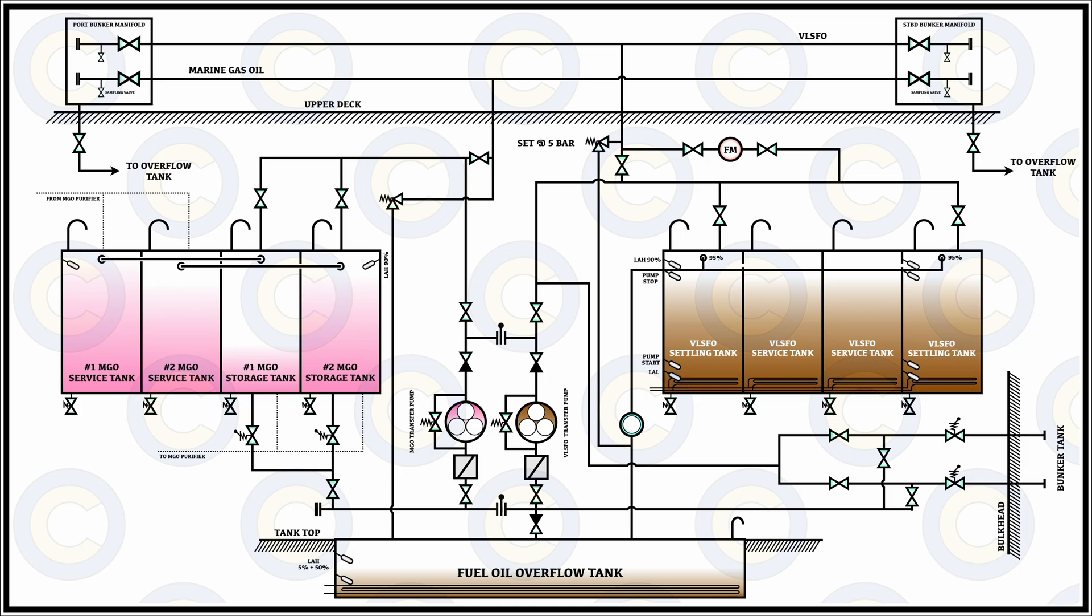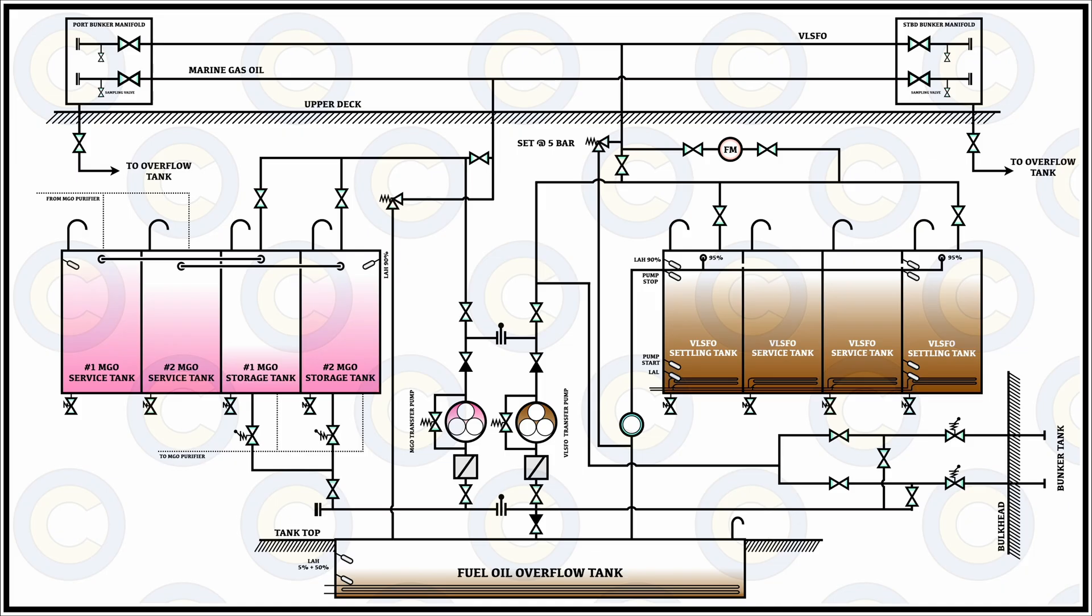Let's say if I was to have certain bunker amount or quantity in my storage tank one and I want to transfer the oil into storage tank two, then basically I line up the suction or the outlet valve - by suction I mean the suction to the pump and by outlet I mean the outlet of the tank. This particular valve, and then as I described earlier the line up, and then opening the filling valve of the number two storage tank - that is how this inter-transfer can take place.